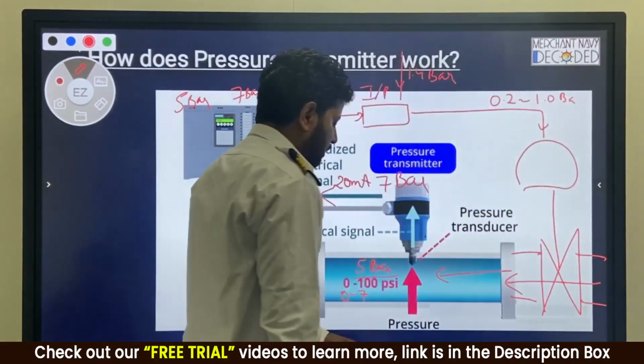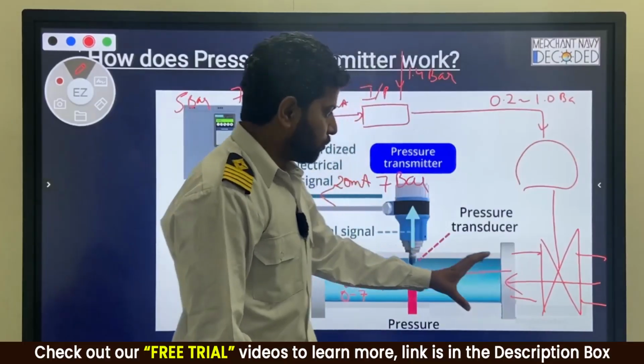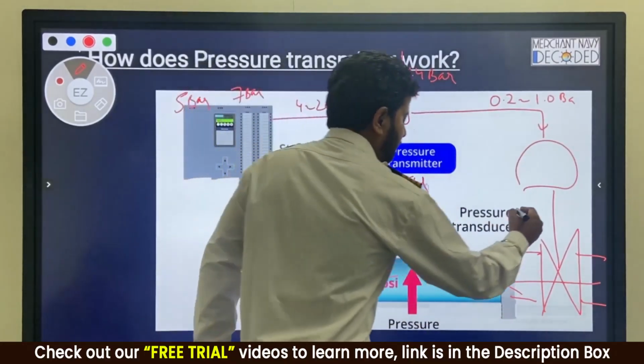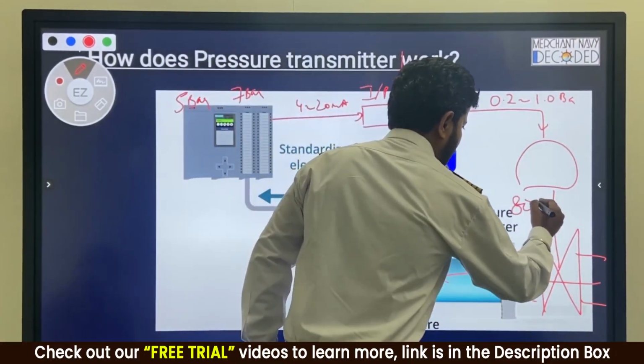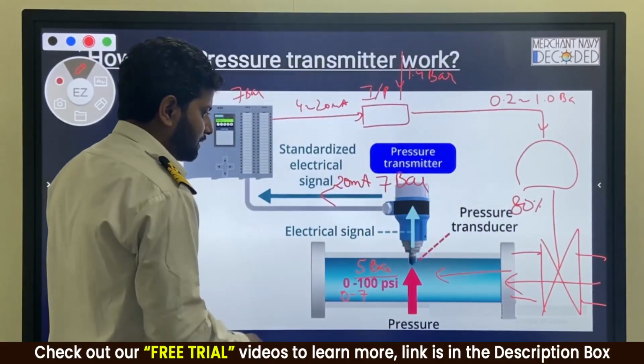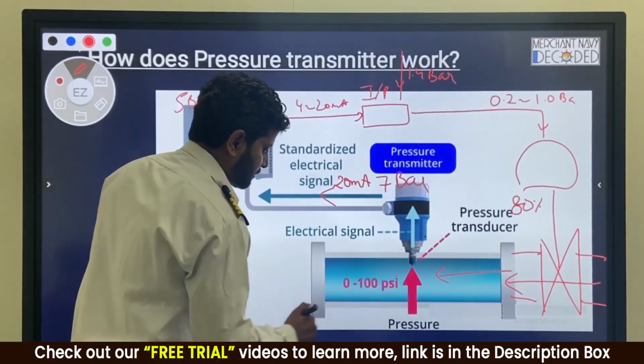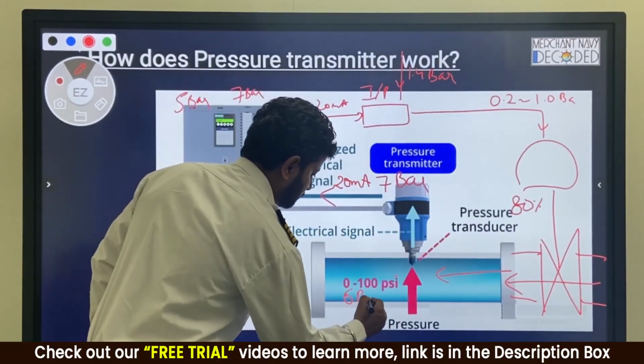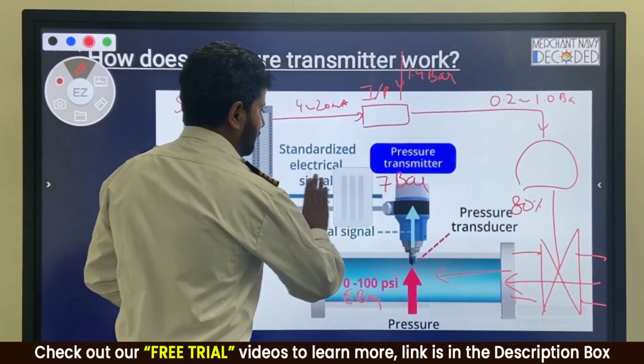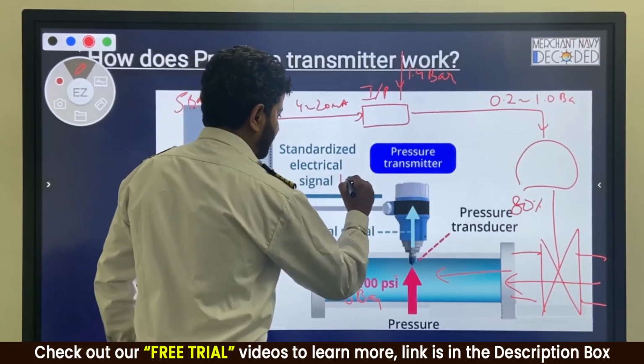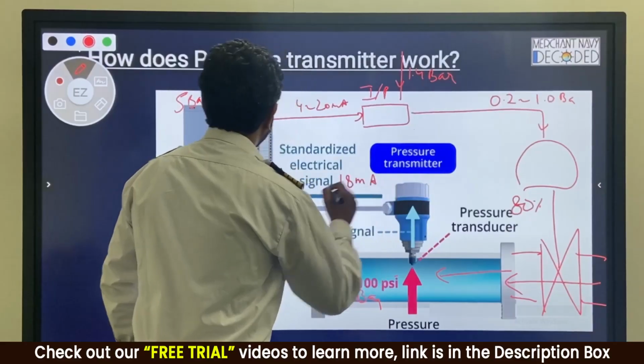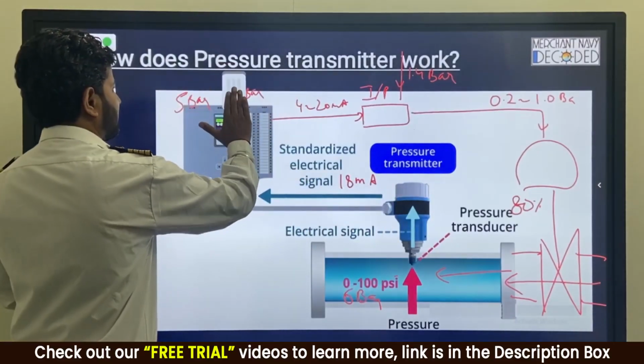And what will it do? It will shut the valve. So the valve which was 100% open maybe will become 80% open now. And suddenly you will see the pressure which was 7 bar has now become 6 bar. The milliamps which was 20 milliamps has now become 18 milliamps. Just an example. Okay, now it is 6 bar.